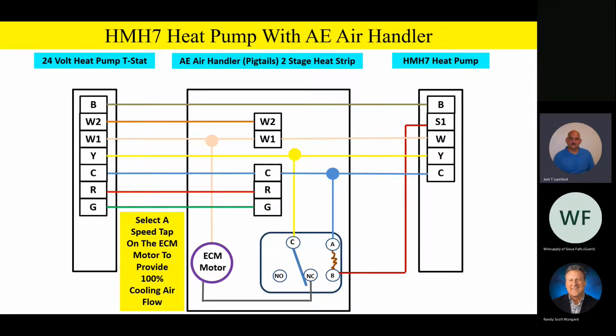Now, team, remember, we're always going to recommend that you have 400 CFM per ton on your high speed or your 100% cooling airflow. So an example would be if it's a 2-ton unit setting outside, that normally closed contact, you need to select a speed tap that's going to give me 800 CFM. If it's a 3-ton unit, that normally closed contact on the relay, we're going to select a speed tap to give me 1200 CFM and so on. So we always want to drive that fan at 100% cooling airflow at 400 CFM per ton of cooling capacity of the outdoor unit. Any questions or comments on that so far?